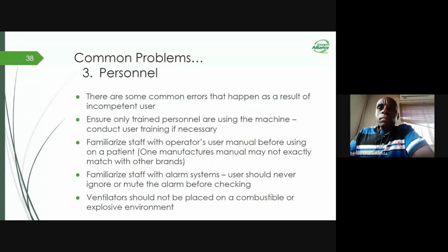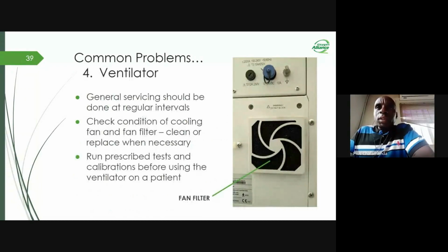Okay, so let's proceed by looking at the ventilator itself as a machine. What are the common problems associated with the ventilator? We have to make sure as engineers that the general servicing of the mechanical ventilator is done at regular intervals. Check the condition of the cooling fan and the fan filter. As you can see in the picture, there is a fan filter there. It is located at the back, at the rear of the ventilator. So you have to check it. If it is very dirty, you can clean it. If it is damaged, you can replace it.